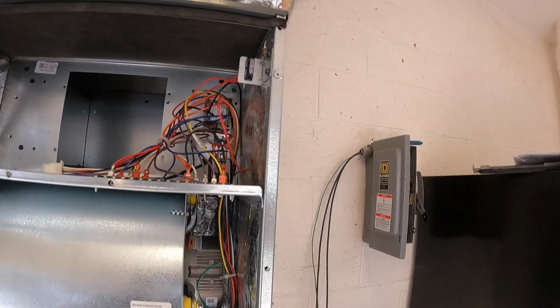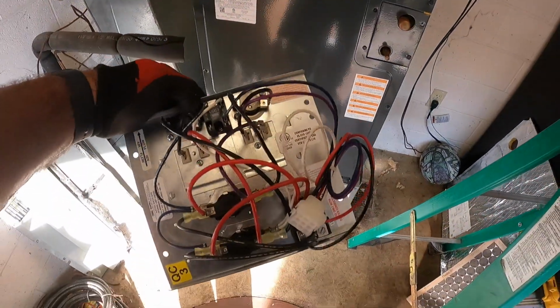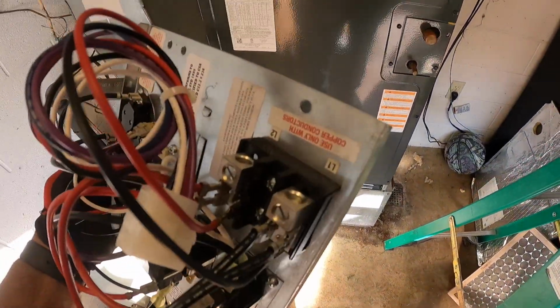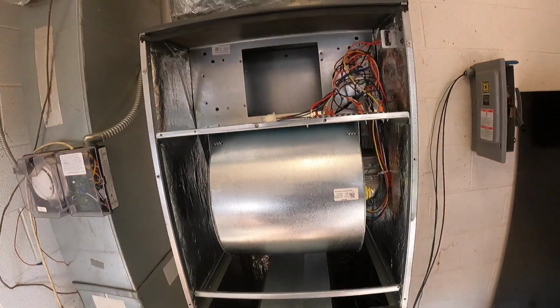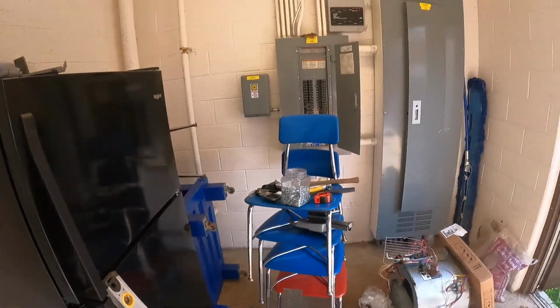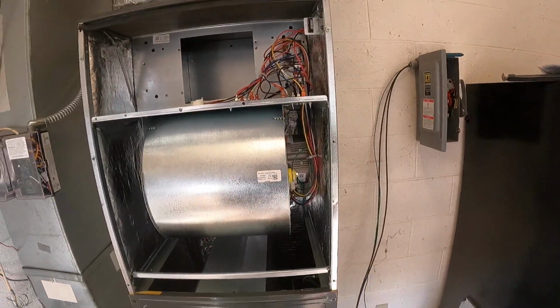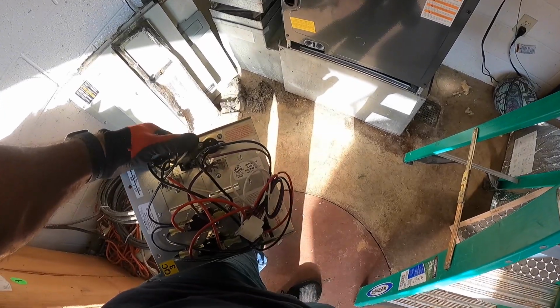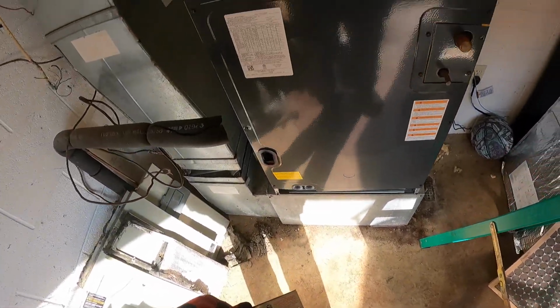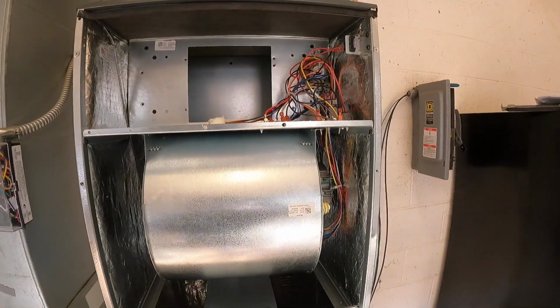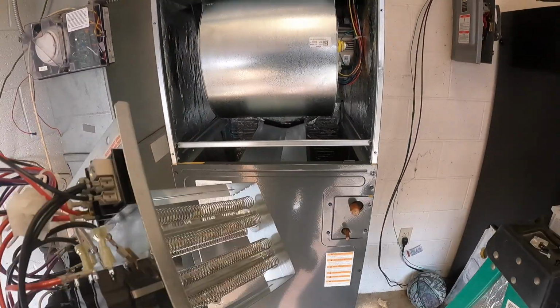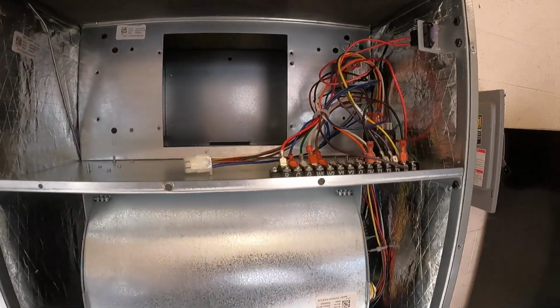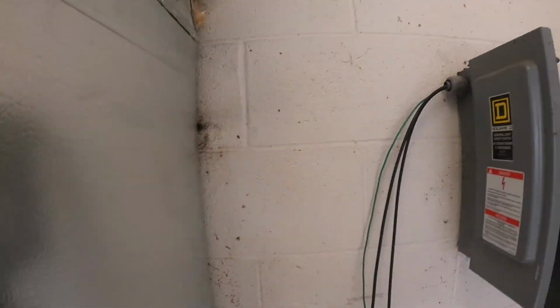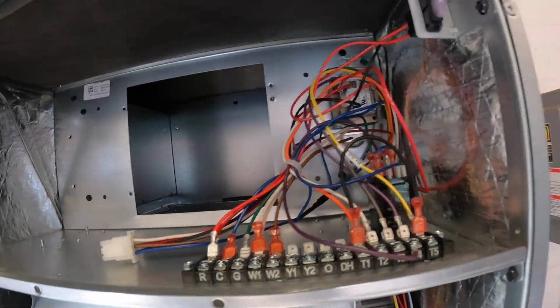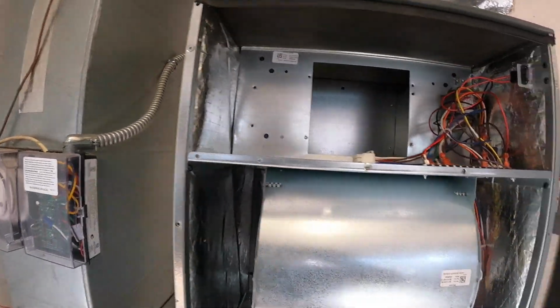So now we're going to have to figure this electrical out. Here's the heat kit — I just got one with lugs on it instead of a breaker. There's no point having another breaker right here when you've got a big disconnect and the main breaker right there. And if it's anything like the junk I've been getting lately, the breaker in your air handler will probably go bad in the first year, or the disconnect, whatever they call those Chinese-made things. So I'm going to put this in, but I think I'll bring my power in right down here and pull a hole in there, since it's coming from there, and that'll be a lot better than wrapping all the way around the thing like before.